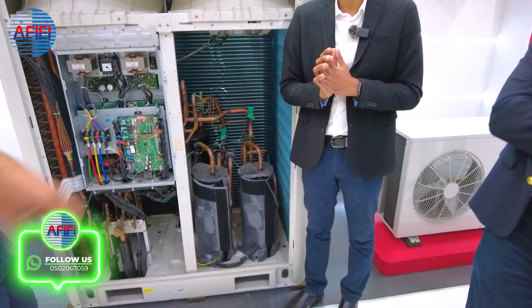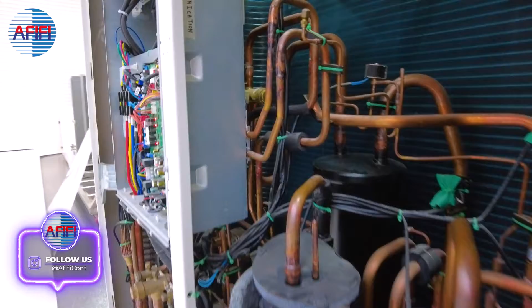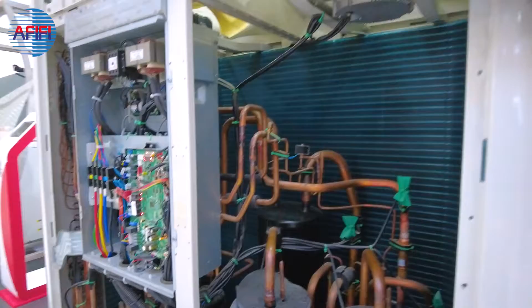Perfect. Yeah, and then there's a non-return valve here so that the discharge doesn't come back, and then it goes into the four-way valve, or reversing valve, because this is a heat pump. All of our VRF units are heat pumps. If it is in the cooling mode, it will go into the condenser. If it's in the heating mode, the pilot solenoid will operate, and the hot gas would go into the indoor units, and the fan will blow. That's why you have a capillary distribution here, because it works as an evaporator in the heat pump.